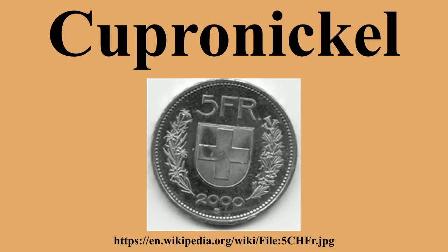They have high resistance to crevice corrosion, stress corrosion cracking, and hydrogen embrittlement that can be troublesome to other alloy systems. Copper nickels naturally form a thin protective surface layer over the first several weeks of exposure to seawater, and this provides their ongoing resistance. Additionally, they have a high inherent biofouling resistance to attachment by macrofoulers living in the seawater.